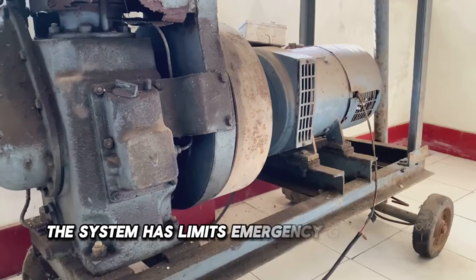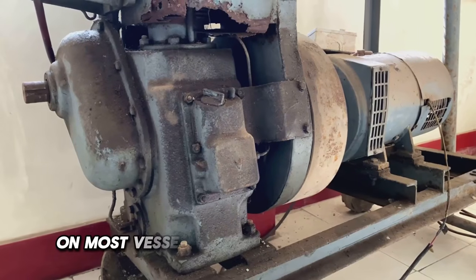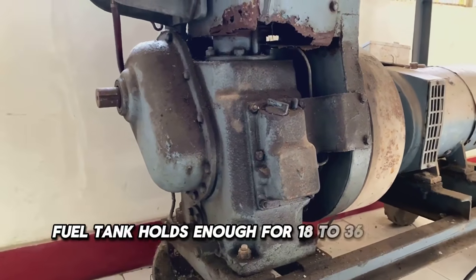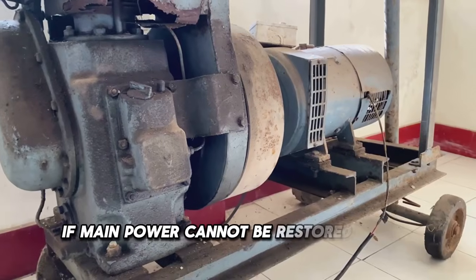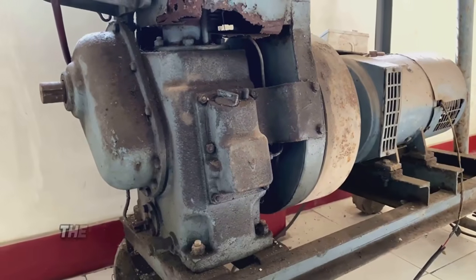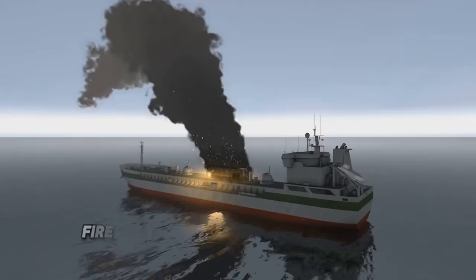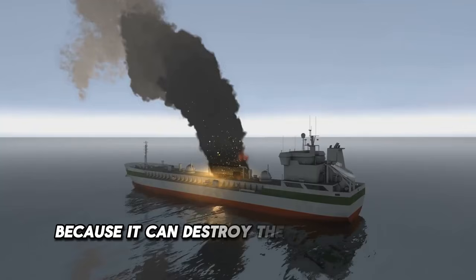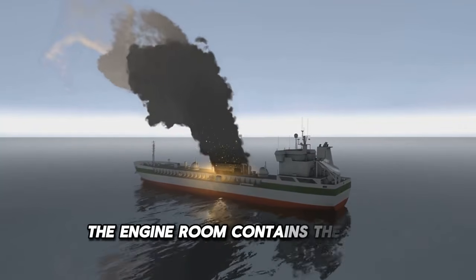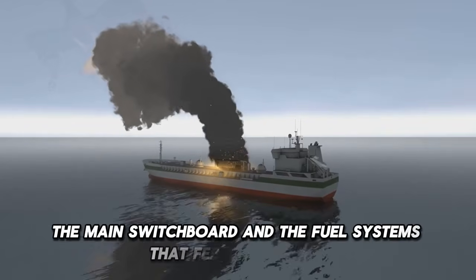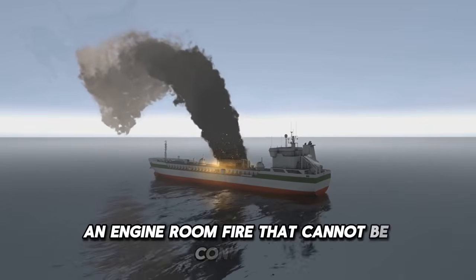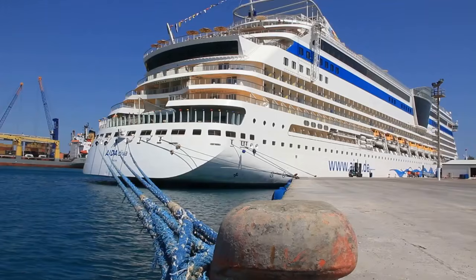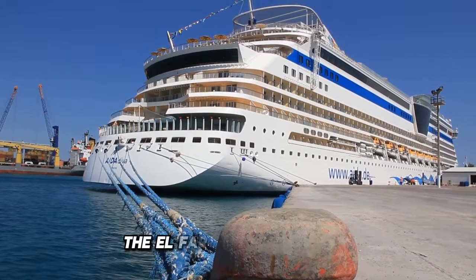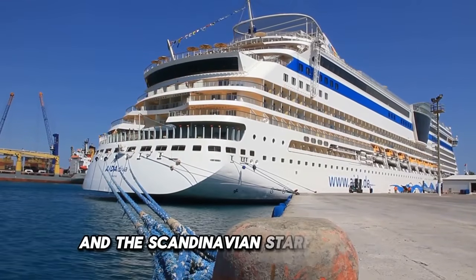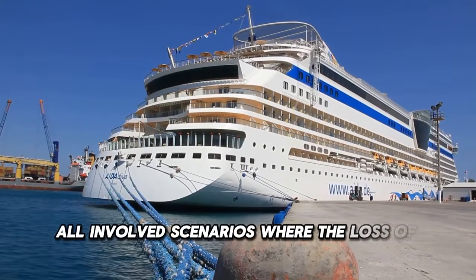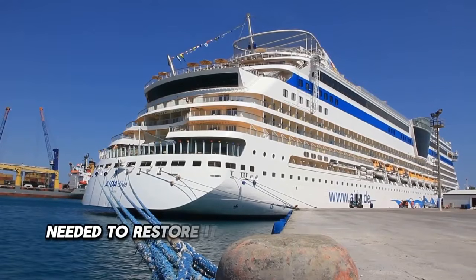The system has limits. Emergency generators have finite fuel capacity. On most vessels, the emergency generator fuel tank holds enough for 18 to 36 hours of operation. If main power cannot be restored within that window, which would be an extreme scenario, the situation becomes significantly more serious. Fire is the most dangerous cause of blackout because it can destroy the systems needed to restore power. The engine room contains the main generators, the main switchboard, and the fuel systems that feed everything. An engine room fire that cannot be contained can render a ship permanently dead in the water. The Costa Concordia grounding in 2012, the El Faro sinking in 2015, and the Scandinavian Star fire in 1990 all involved scenarios where the loss of power, or the loss of the systems needed to restore it, directly contributed to the outcome.